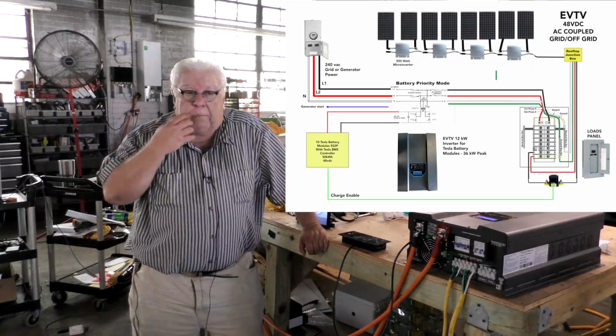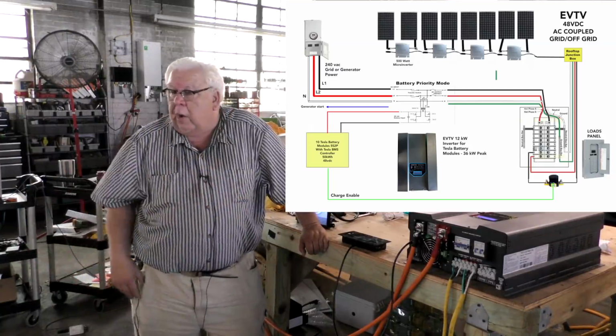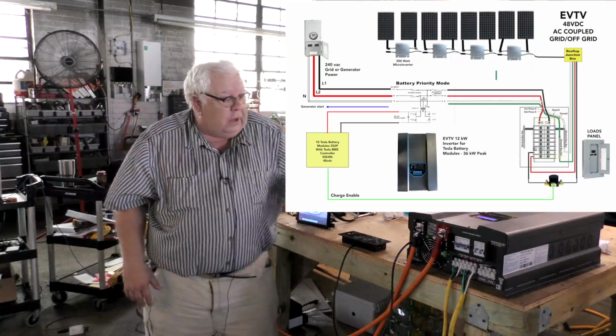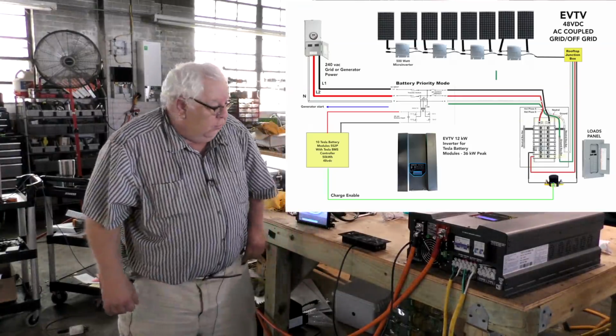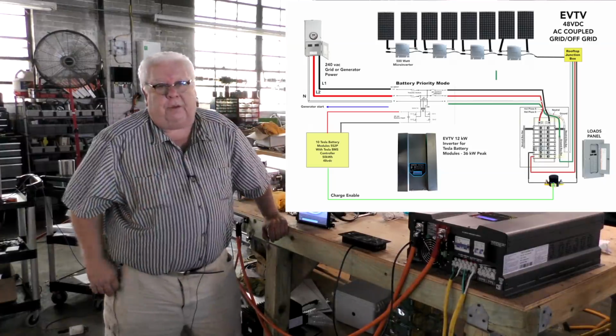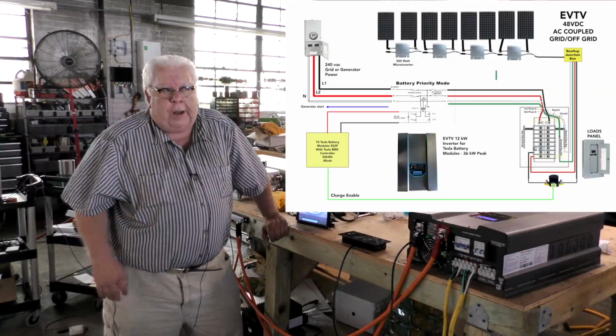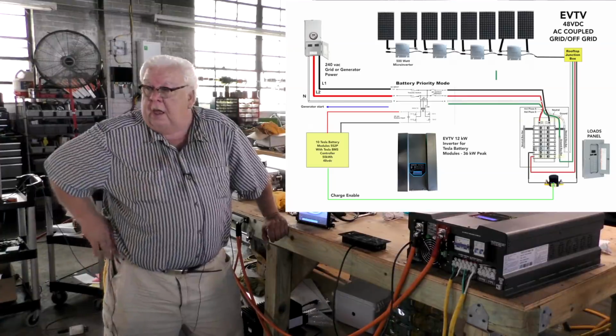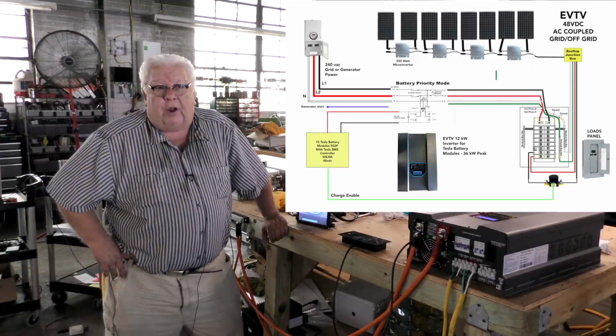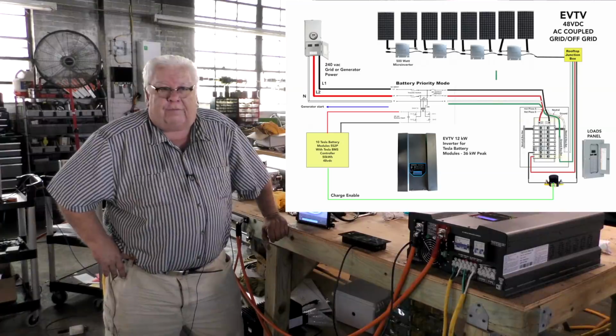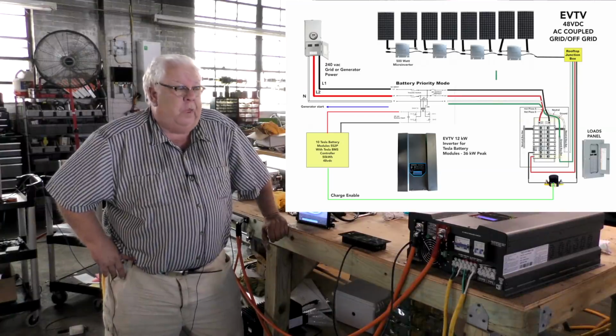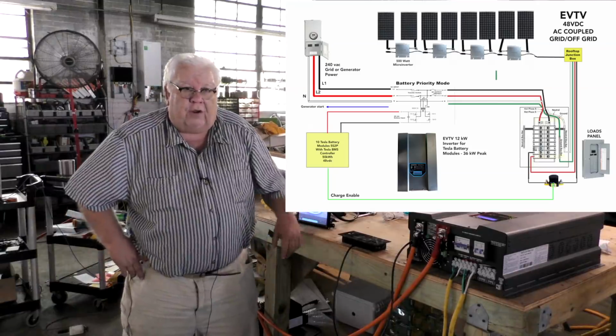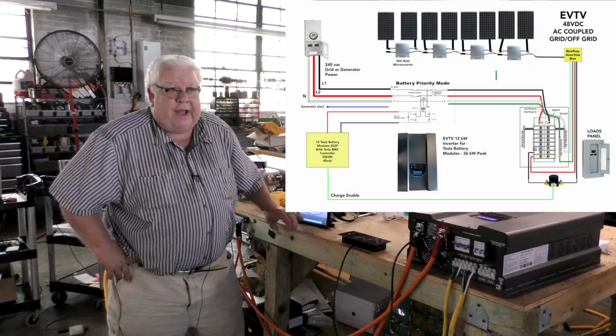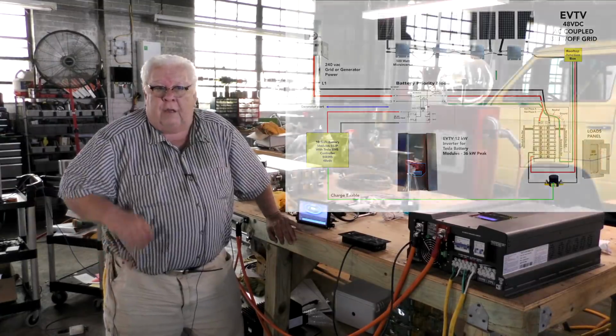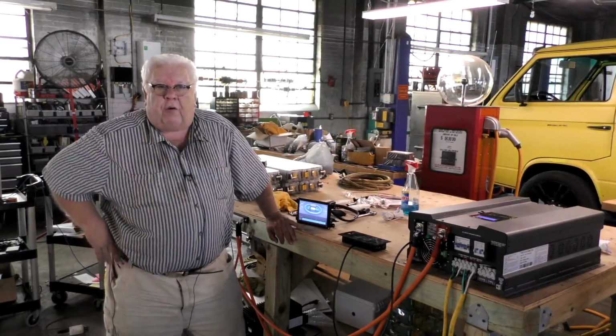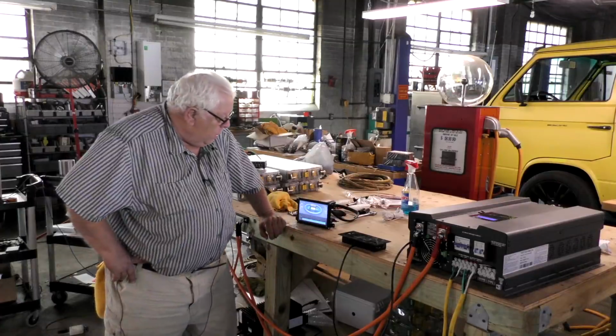I've been told completely that what we're doing right here, right now, will not work. And in fact, the company that makes this device told me it had no possibility of working this way. Well, right now, I've got their undivided attention because it is working that way and working very well. And so their product is capable of something they didn't even know it would do. Off of their AC input, they can charge at about 5 kilowatts. I've had this at 13.5 kilowatts running off of grid-tied inverters that are synced to the output of this inverter.